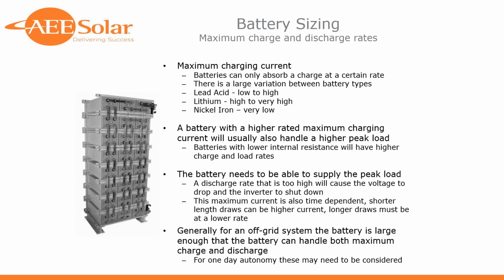when you have a power outage. When it's grid tied in a backup system, a purely backup system, when the system is grid tied, the battery is just going to be sitting at full charge, and it's not an issue. It's only when the power goes off, utility goes off, and you're running the system off grid that this becomes an issue.